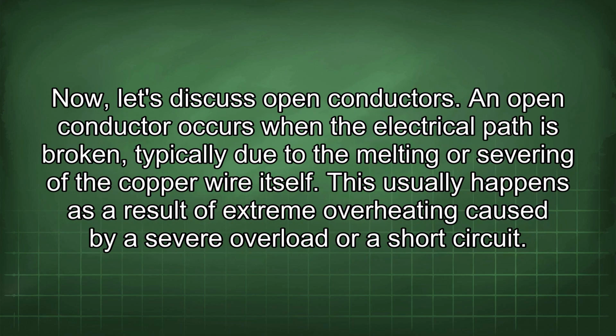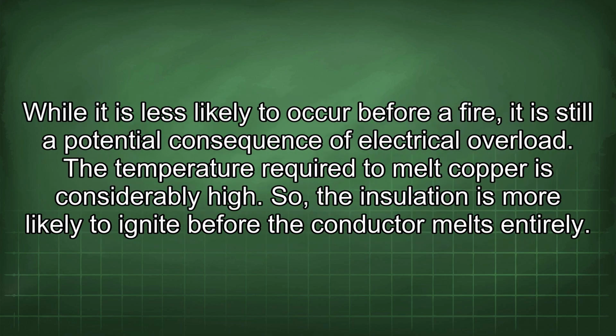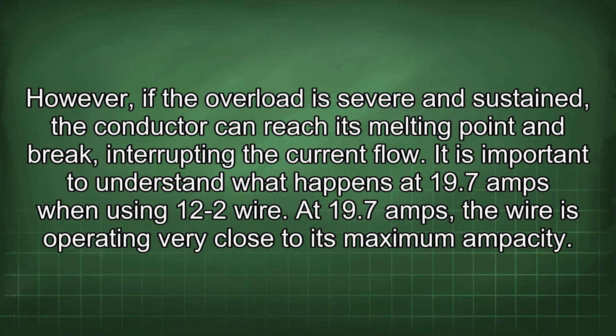Now let's discuss open conductors. An open conductor occurs when the electrical path is broken, typically due to the melting or severing of the copper wire itself. This usually happens as a result of extreme overheating caused by a severe overload or a short circuit. While it is less likely to occur before a fire, it is still a potential consequence of electrical overload. The temperature required to melt copper is considerably high. So, the insulation is more likely to ignite before the conductor melts entirely. However, if the overload is severe and sustained, the conductor can reach its melting point and break, interrupting the current flow.